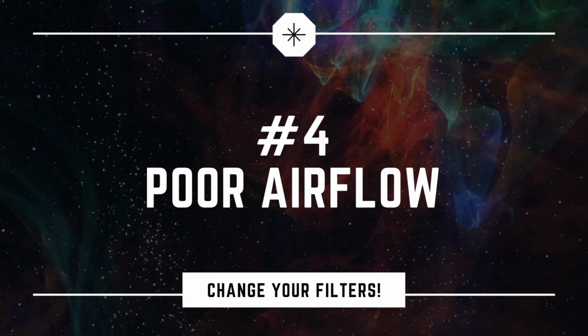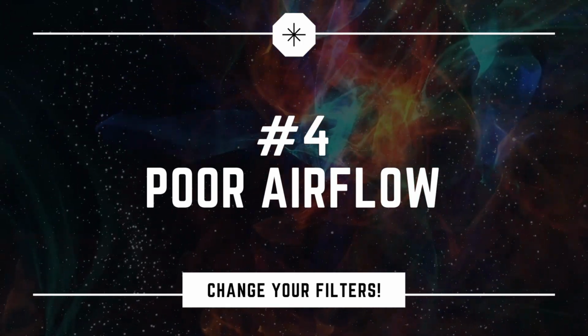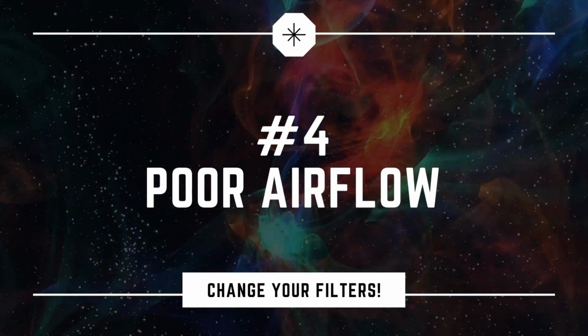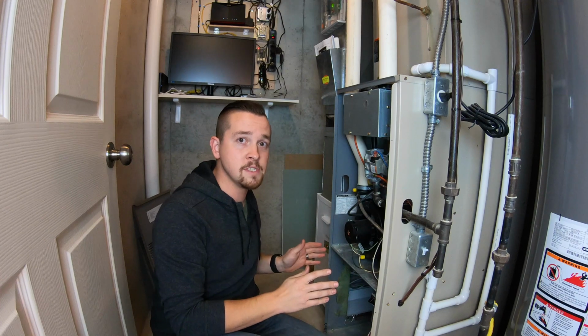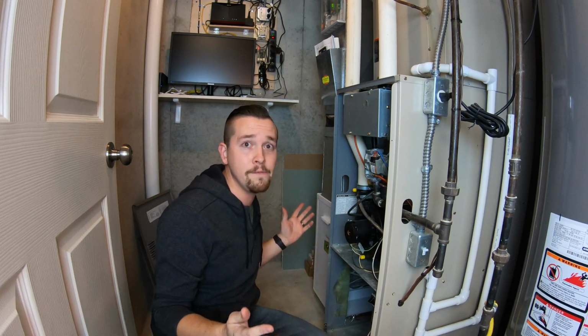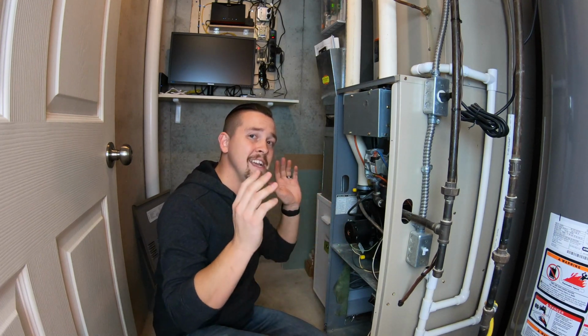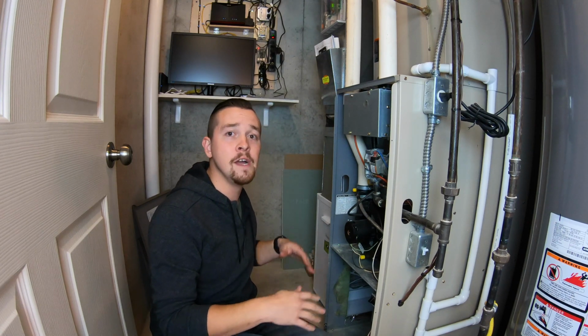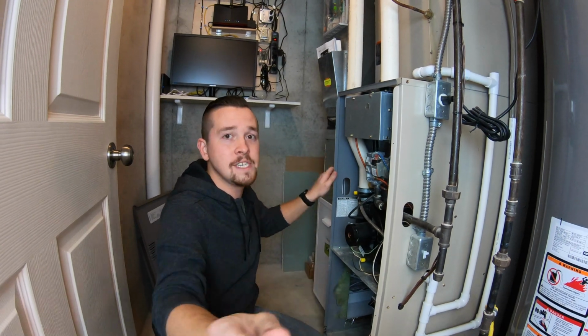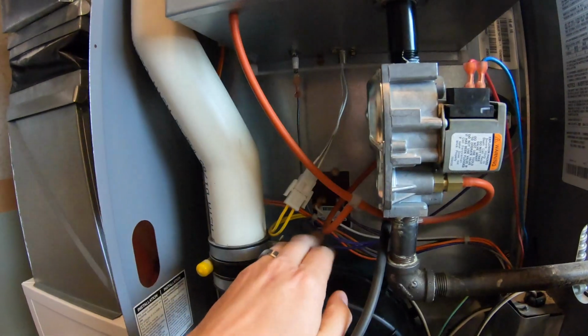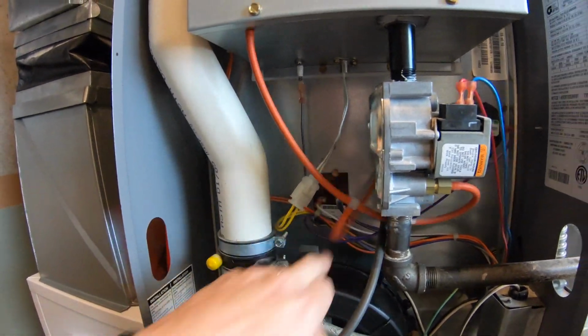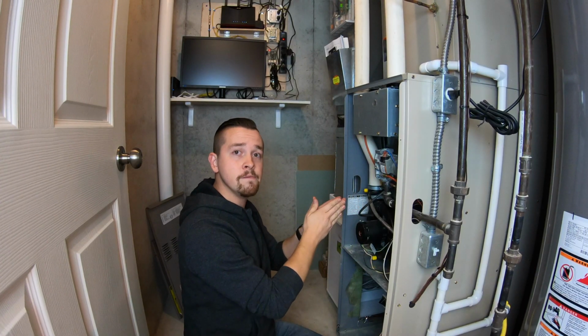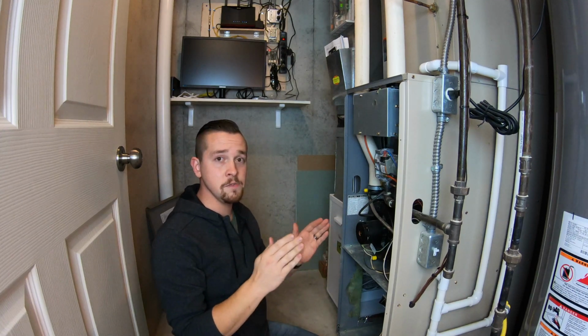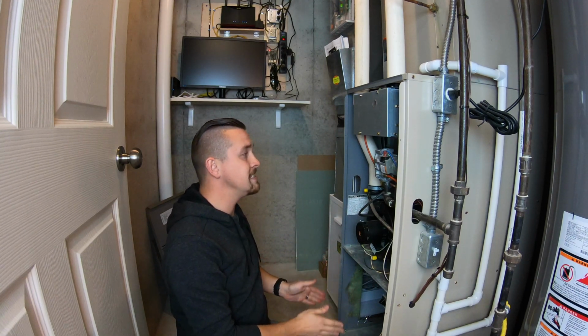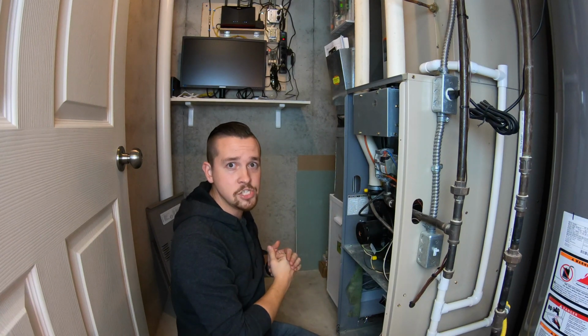Number four is poor airflow. There's several different reasons you could have poor airflow, but generally speaking, what's gonna happen is your furnace will light and it'll run for a little bit, and then it'll get too hot, it'll turn itself back off on safety. So this guy right here is the high temperature limit. If that high temperature limit is tripping for some reason, then that means that you've got a condition that isn't allowing enough air across the heat exchanger.